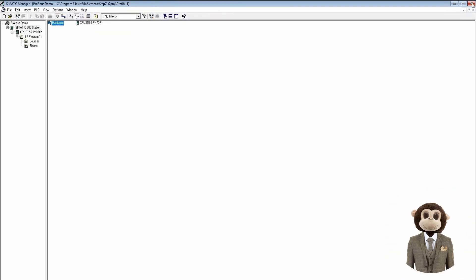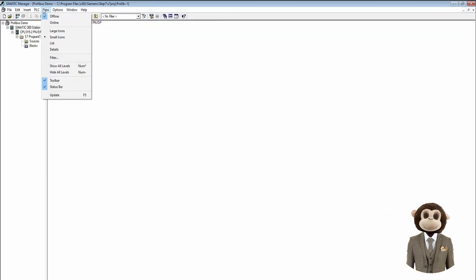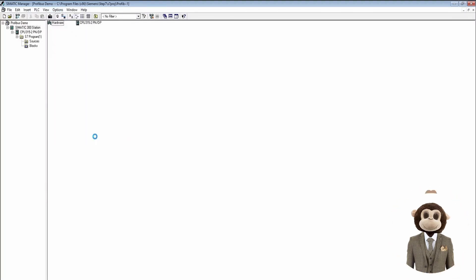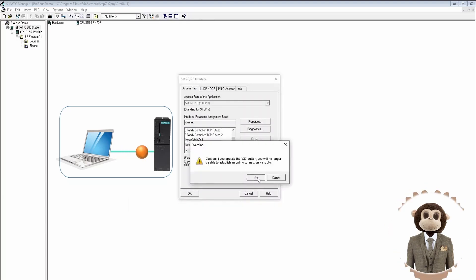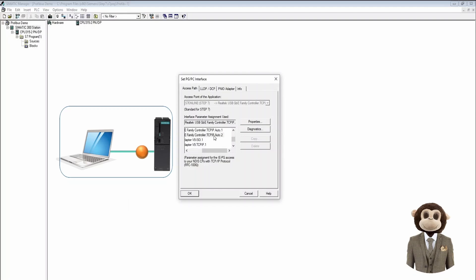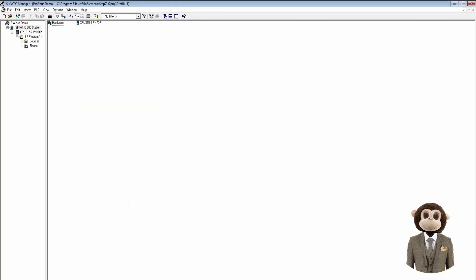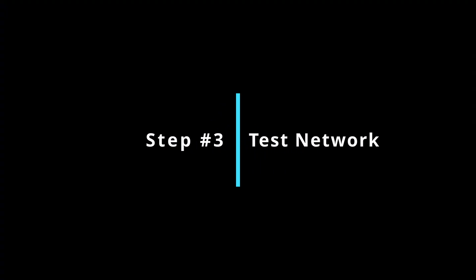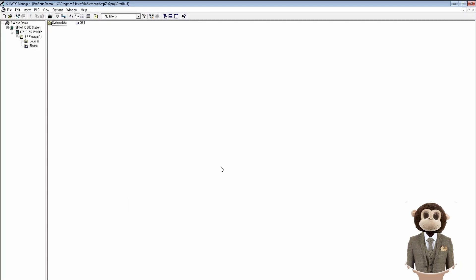We save and close, then set up our connection to the PLC by going to Options > Set PG/PC Interface and selecting the network adapter on the PC that is connected to the PLC. We can see in the bottom that we are going to be using that network adapter. From here we download to the PLC, and the PLC is now set up.